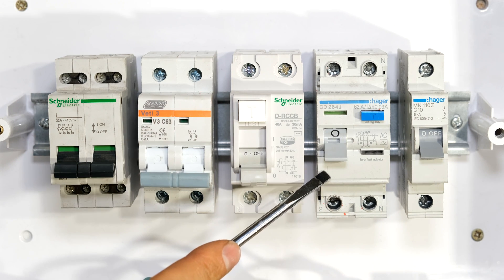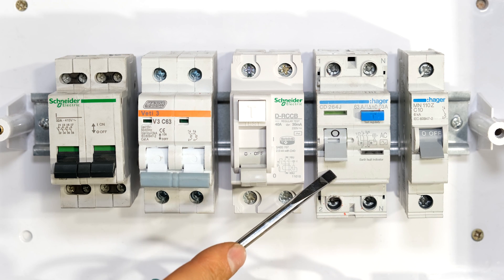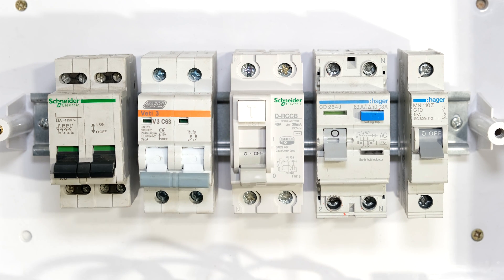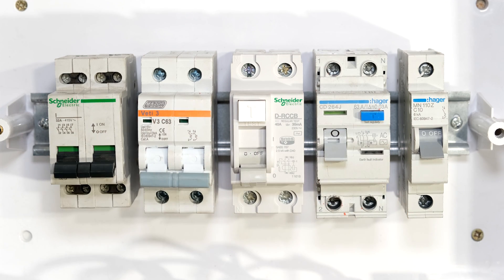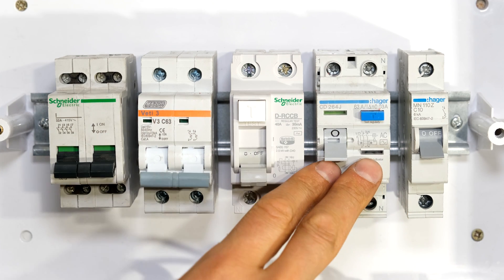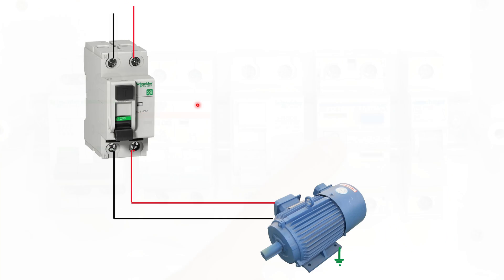One of the reasons why it's called an earth leakage circuit breaker is because if your live current is higher than your neutral current, it means some current is being lost to an earth connection. Therefore there becomes an imbalance and this trips.